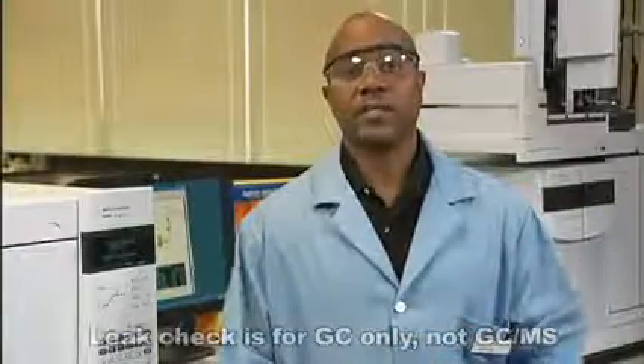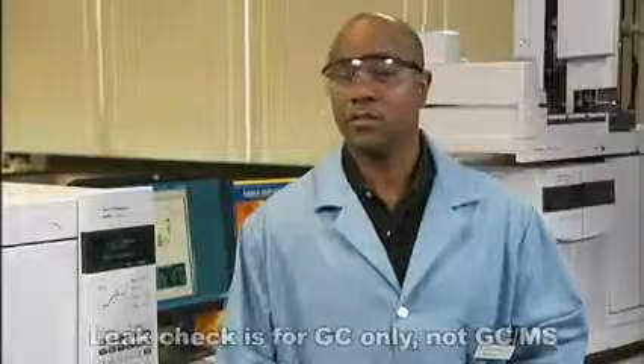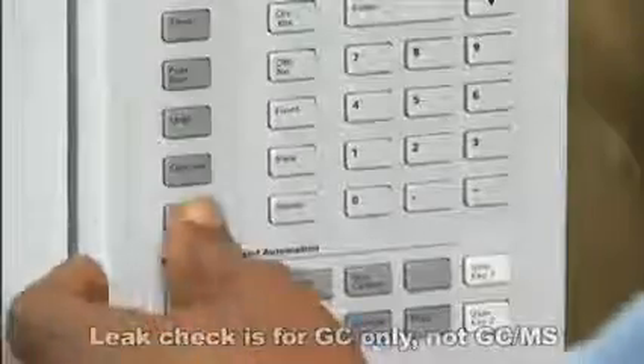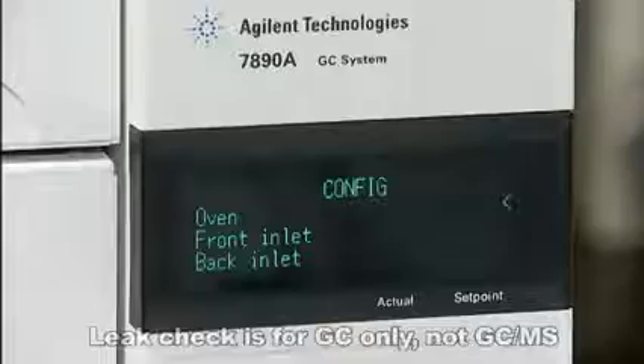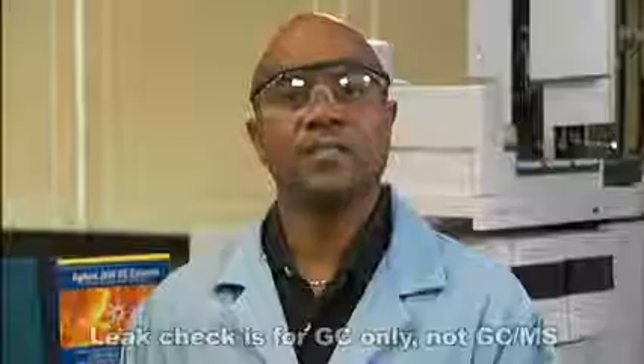First, we need to check that the column dimensions are entered accurately into the GC. Next, set the inlet to splitless mode.